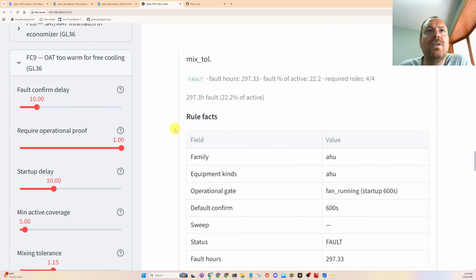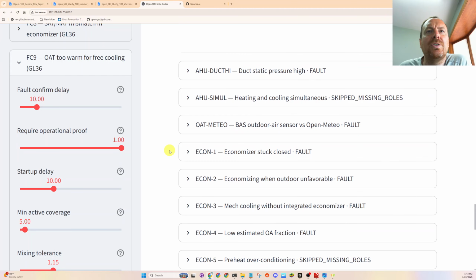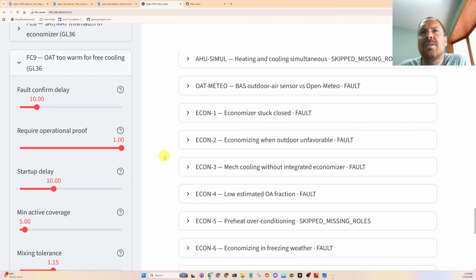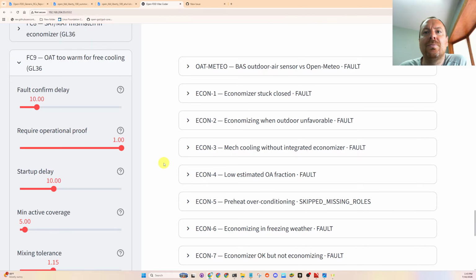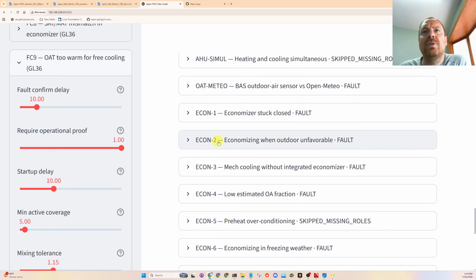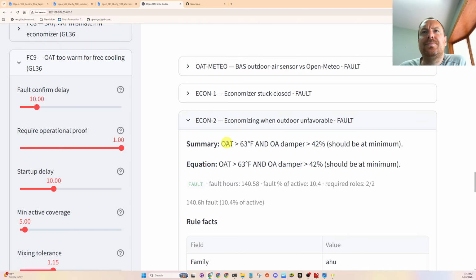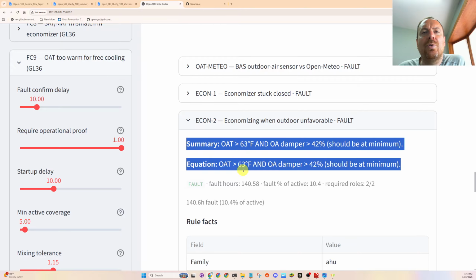Okay, so let's look at one of these other economizer rules. So maybe I'll have to look at this too. We do have a few more economizer equations. Here's another economizer equation: economizing when outdoor air is unfavorable. Outside air temperature is greater than 63. This needs to be rewritten for dew point if we have it.